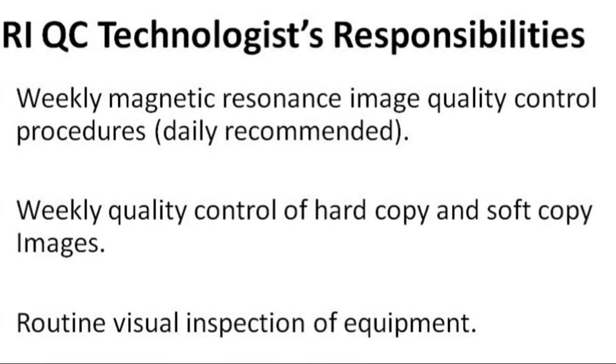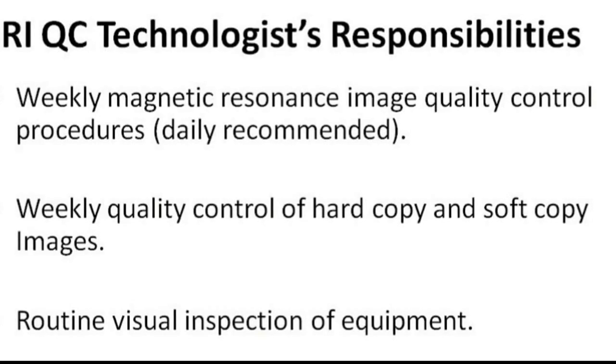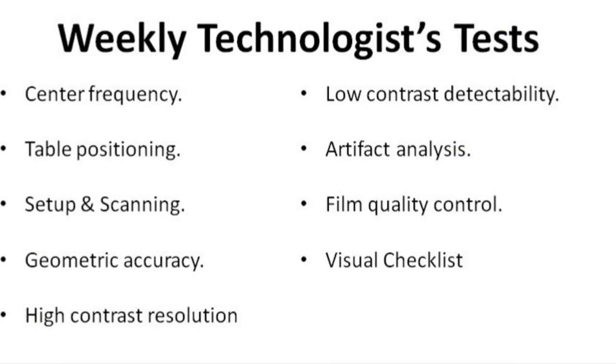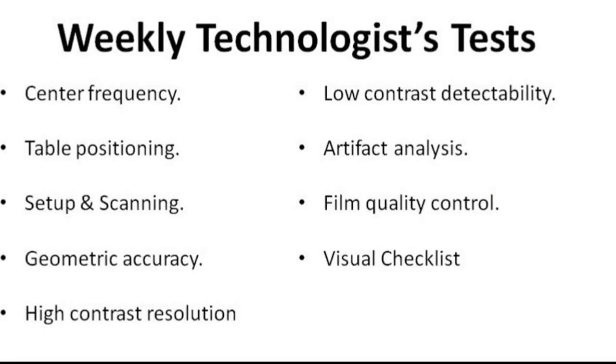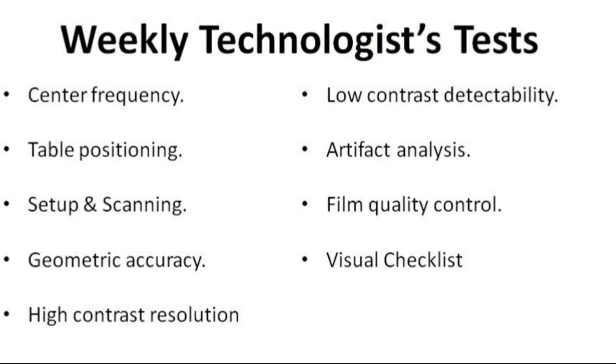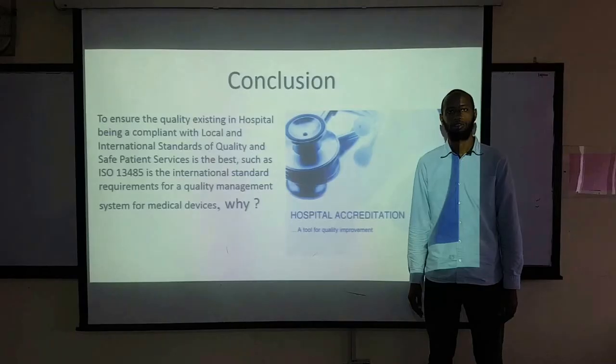MRI quality control technologist responsibility suggests that weekly magnetic resonance image quality control procedures are recommended daily. Weekly quality control of hard copy and soft copy images. Routine visual inspection of the equipment. Weekly technologist tests: center frequency, table positioning, setup and scanning, geometric accuracy, high contrast resolution, low contrast detectability, artifact analysis, film quality control, and a visual checklist.